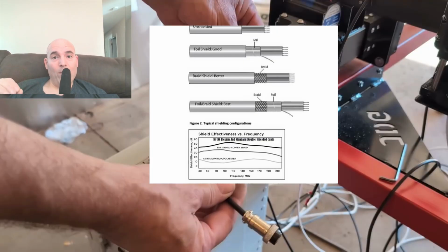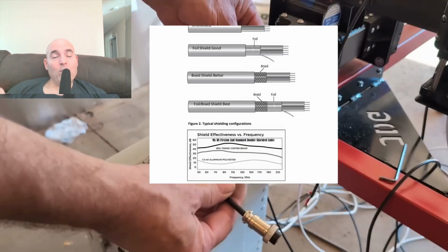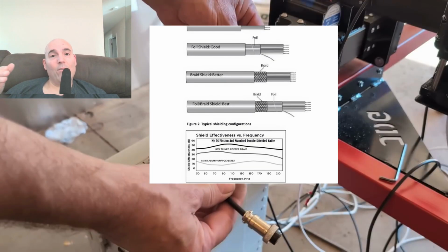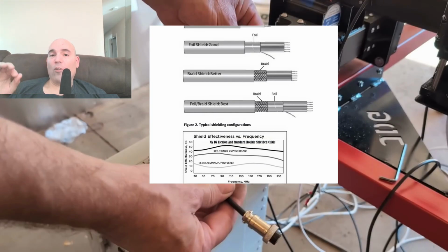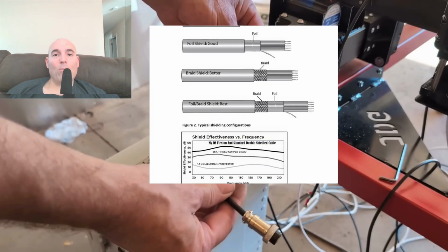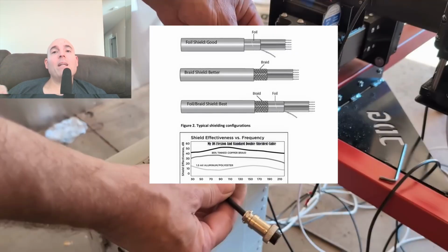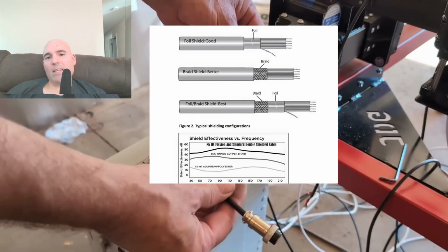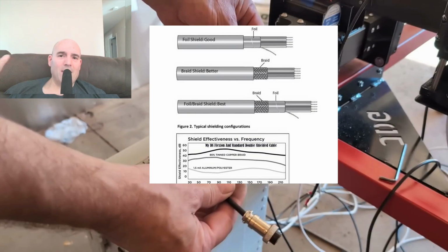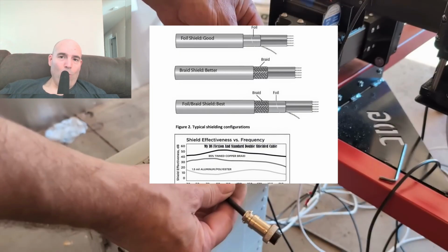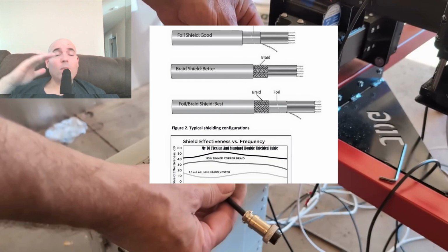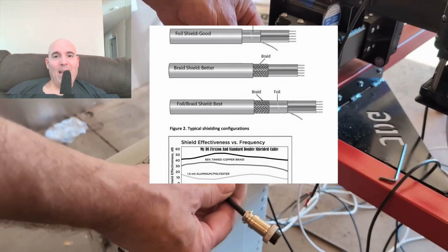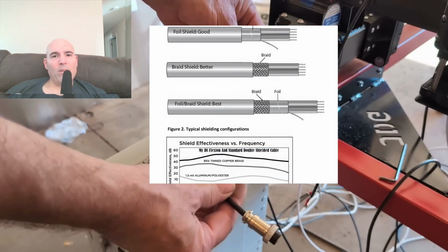So if we're dealing with a switch on a plasma robot, which generates the largest amount of EMI on any robot there is, you will want to use, just like all the other CNC production robots, double shielded cable to mitigate both forms of high and low frequency EMI. Now, I do get arguments now and then that my robot only sees this, or technically robots only are in high frequency. You guys forget one thing. And when I bring this up, there's never an argument to it.